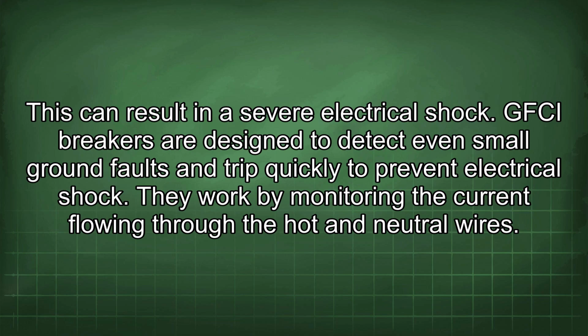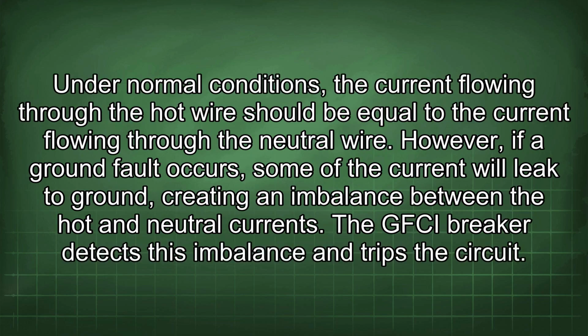GFCI breakers are designed to detect even small ground faults and trip quickly to prevent electrical shock. They work by monitoring the current flowing through the hot and neutral wires. Under normal conditions, the current flowing through the hot wire should be equal to the current flowing through the neutral wire. However, if a ground fault occurs, some of the current will leak to ground, creating an imbalance between the hot and neutral currents. The GFCI breaker detects this imbalance and trips the circuit.